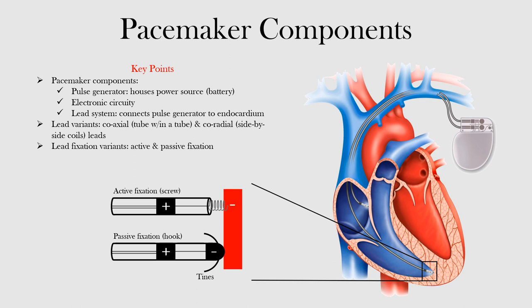The leads deliver a depolarizing pulse to the myocardium. These leads are also capable of sensing intrinsic electrical activity, which we will discuss further in a later lecture. The leads are introduced into a larger vein, such as the subclavian vein, and then guided into the heart where they contact and interface with the endocardium.